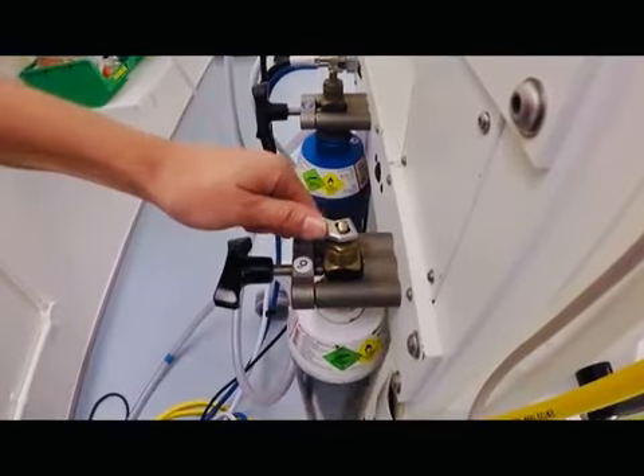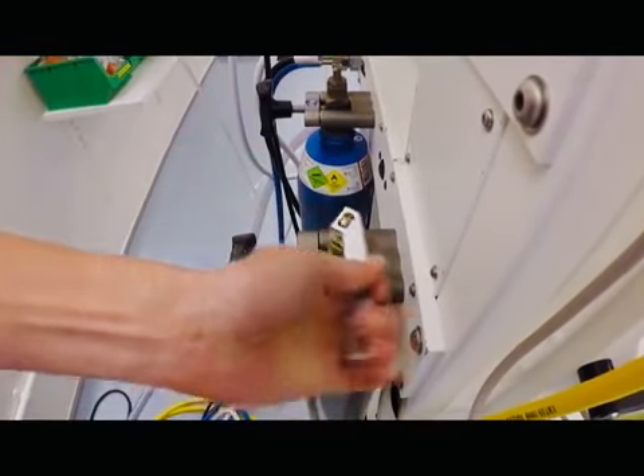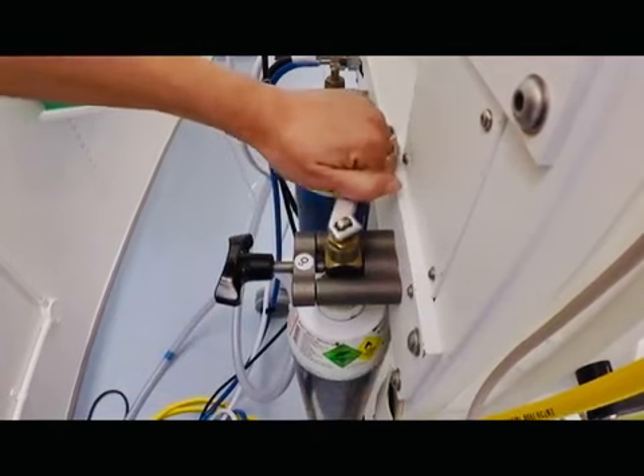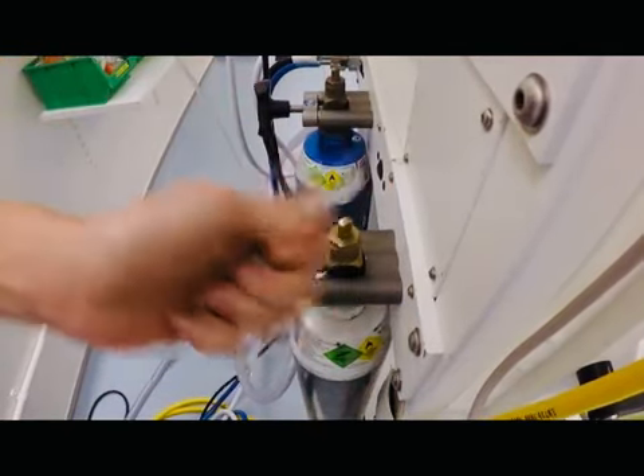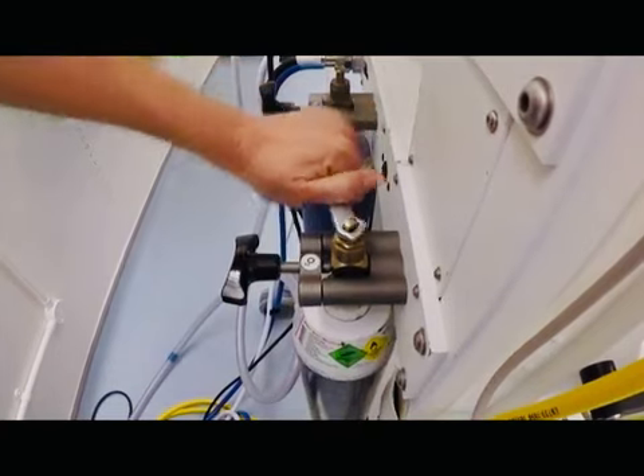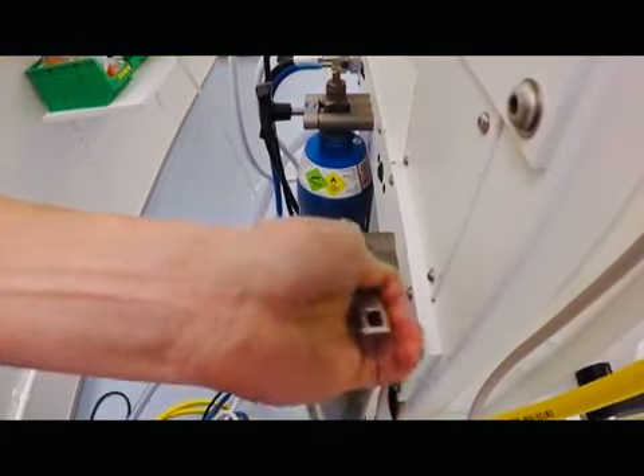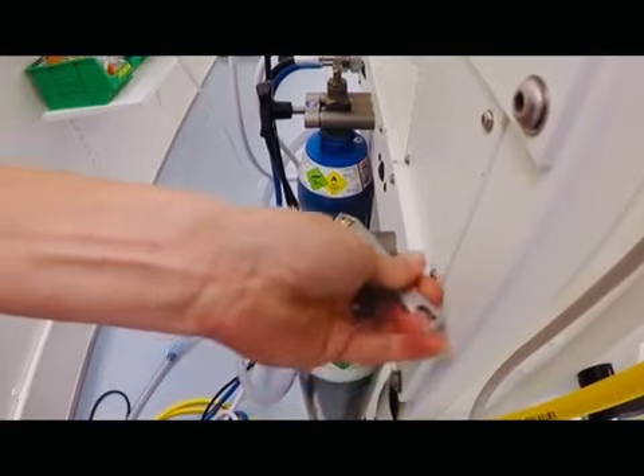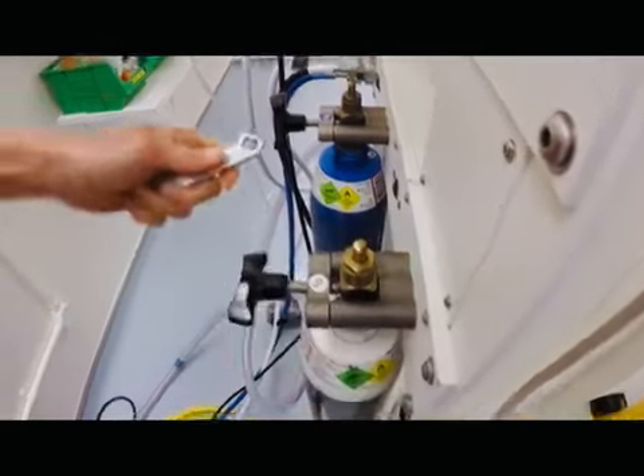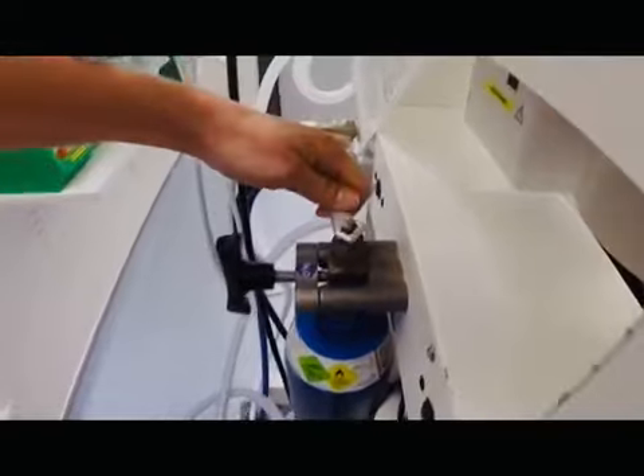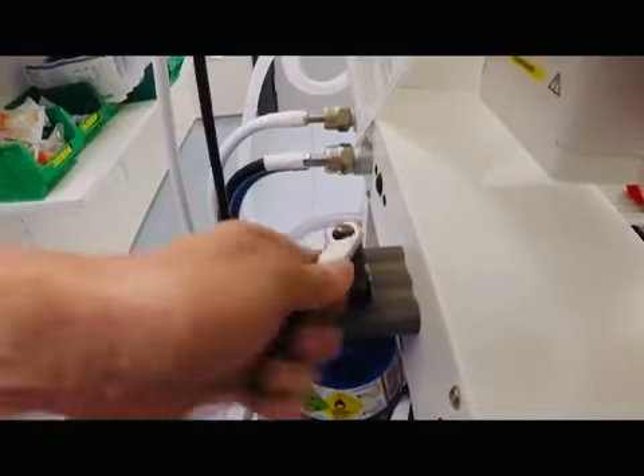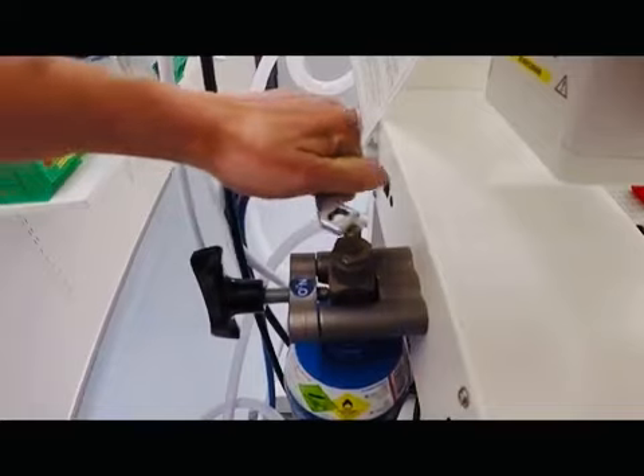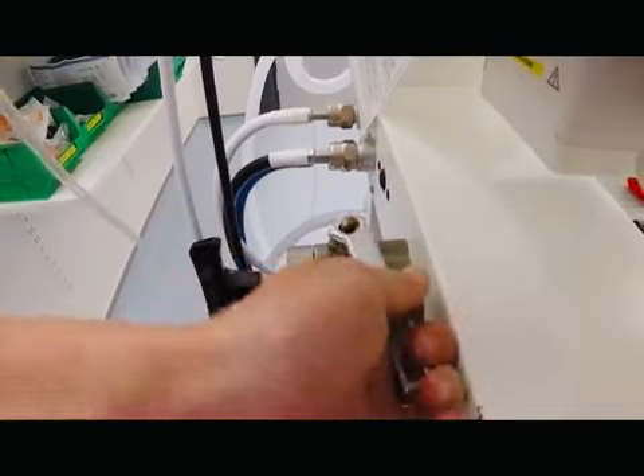Next, check that an alternative gas supply in the form of cylinders is available on the back of the machine in case of pipeline gas failure. Oxygen should always be available, with the option of nitrous in addition. Each cylinder should be turned on in order to check the level. Some cylinder keys will show which way to turn on the cylinder by showing an on-off engraving on them. If not, turn the cylinder on fully so that you can be sure which way to turn the cylinder off completely after checking each level, thus avoiding exhausting the cylinder.